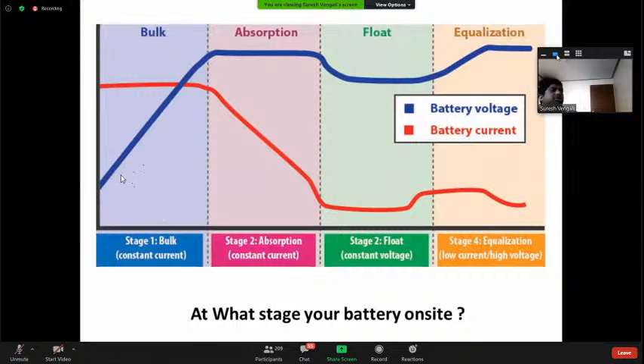In the initial phase, this is constant current. When you measure it, as you come with constant current, you are increasing your cell voltage from about 2 volts, slowly increasing to 2.25 volts, then maintaining that voltage. After that, you have your float voltage and your equalization voltage conditions. Float is 2.25 and equalization is 2.75. This is how your battery goes through its 4 cycles.